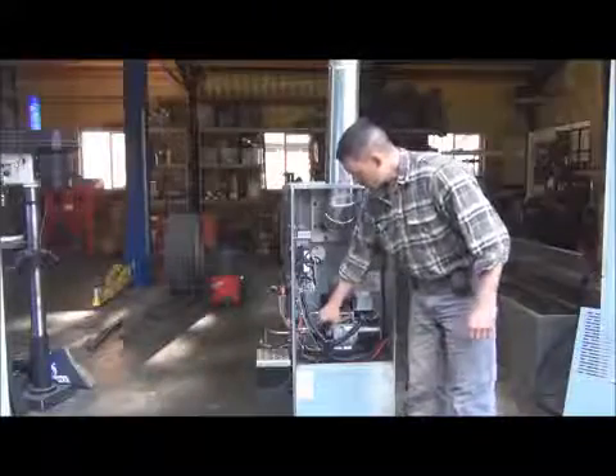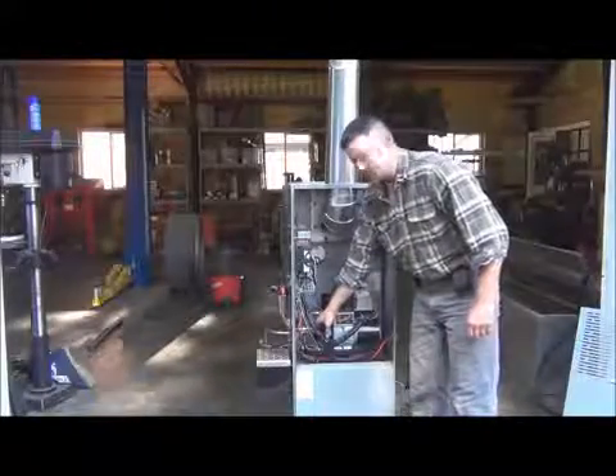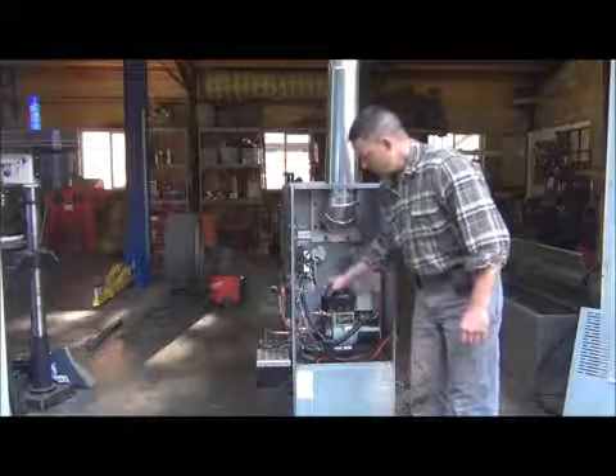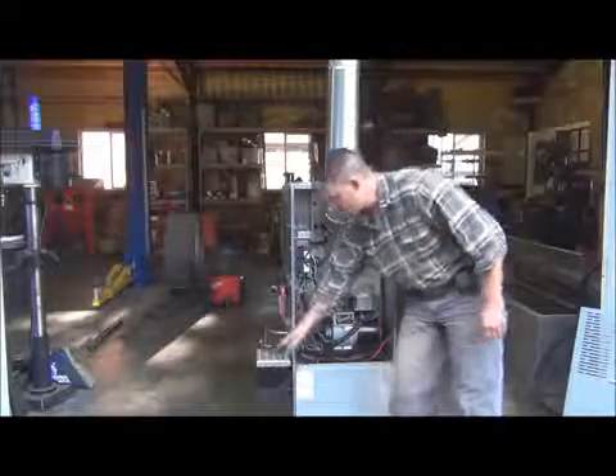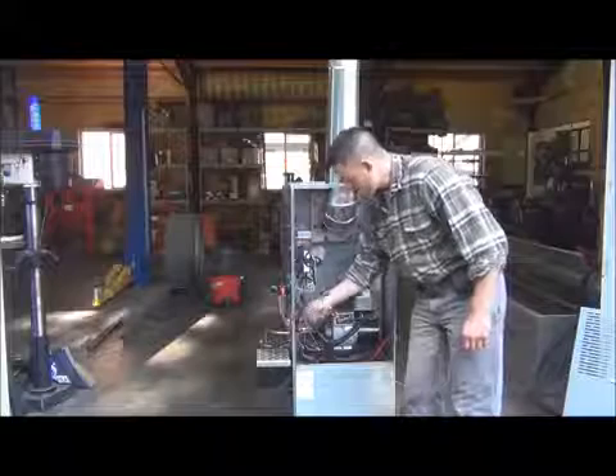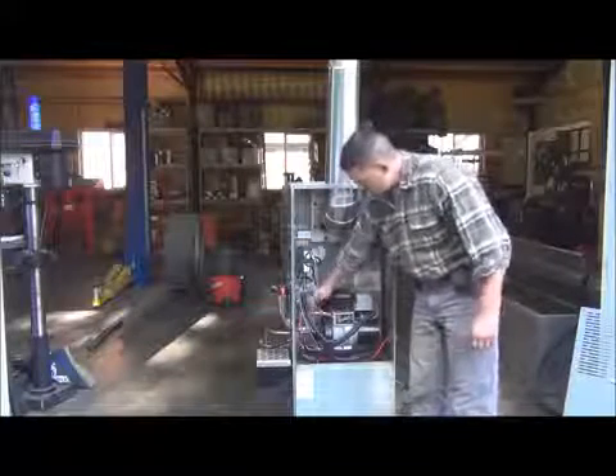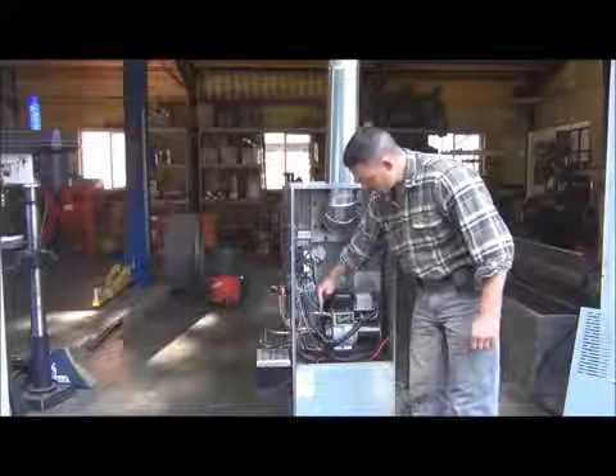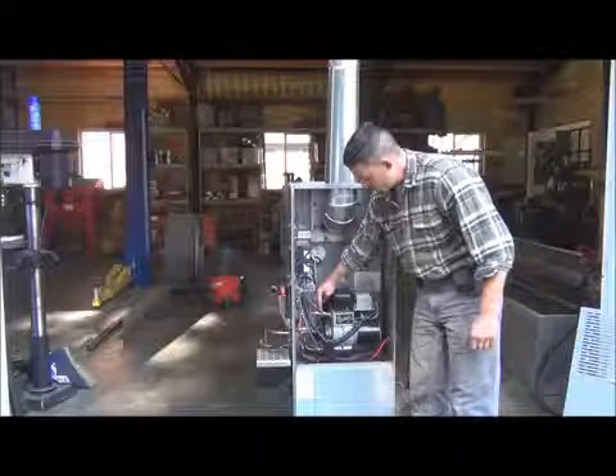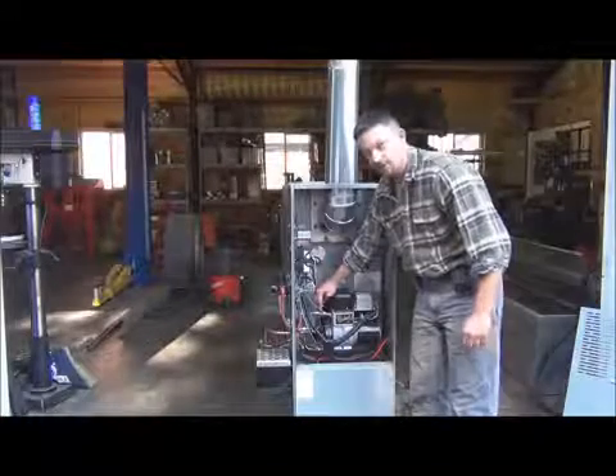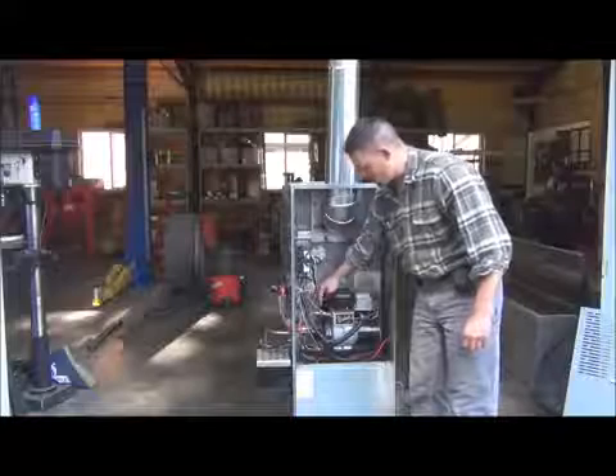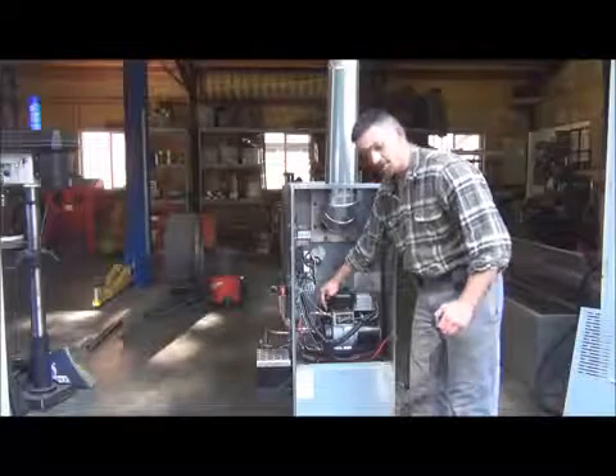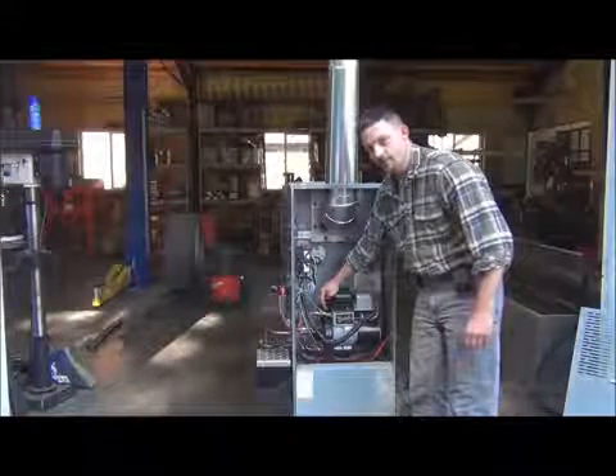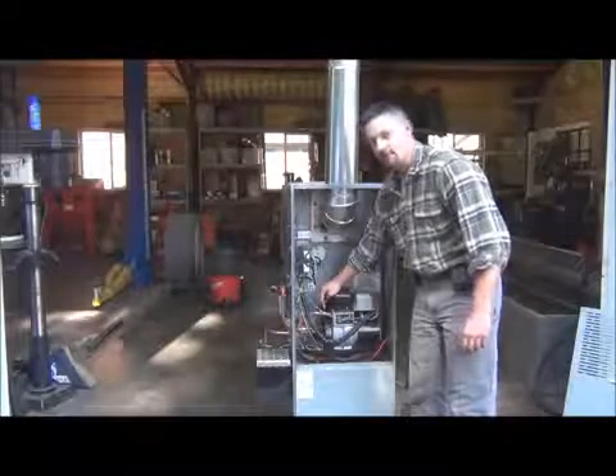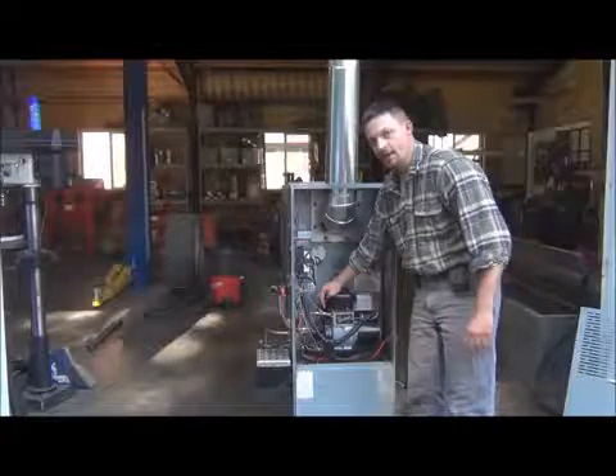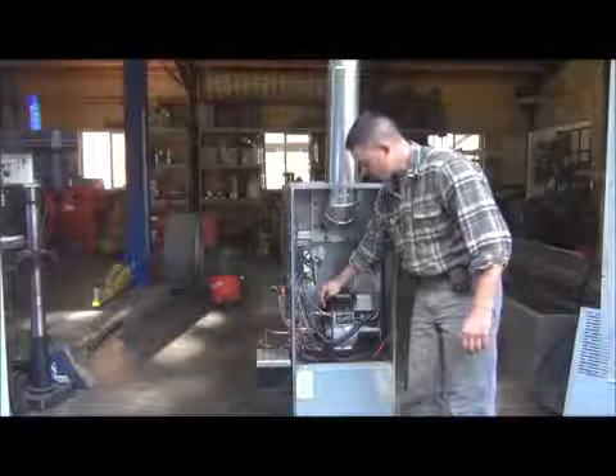Now for the fuel system in here, I've reused the existing oil pump that's on the side of the burner. And this oil pump continuously recirculates oil from this tank right here and pumps it back into the tank. It sends it right through this loop right here where this brass T is, and then the siphon nozzle draws its oil from this T. So we're actually circulating a lot of oil through this loop, and then the siphon nozzle just draws a very small amount through it. I have it set up right now to run at about 1 gallon an hour, so it consumes approximately 1 gallon of waste oil for every hour.